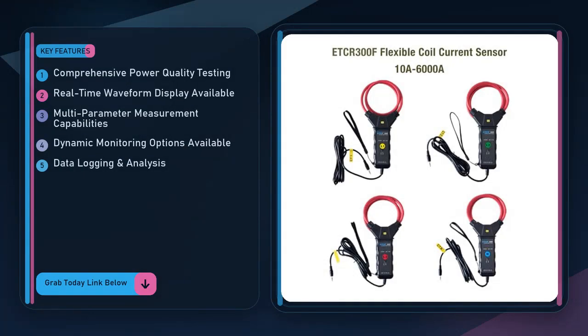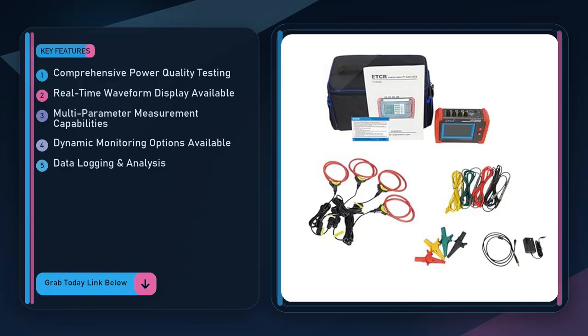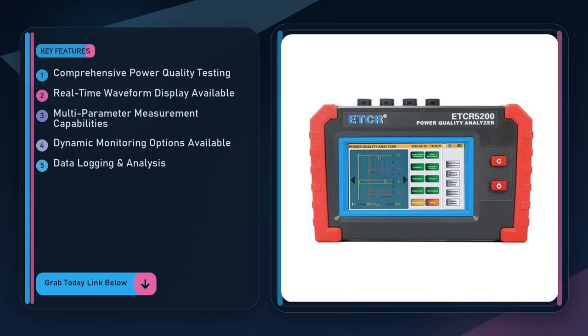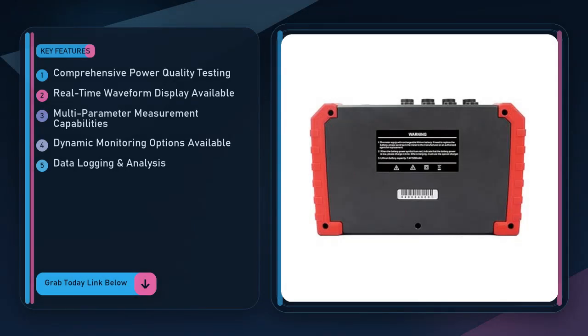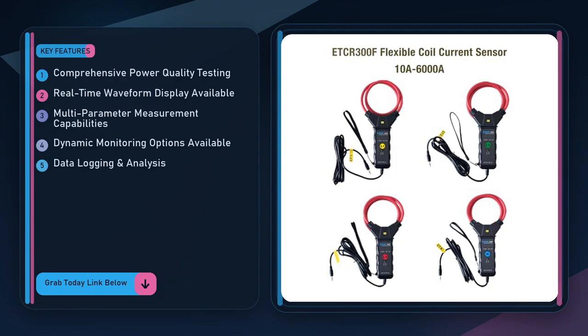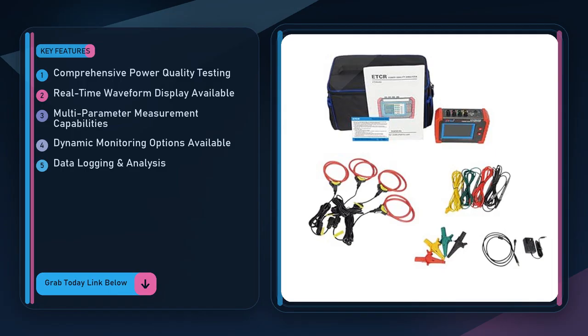Let's get into a couple of concrete scenarios to illustrate the value. A plant manager I spoke with was dealing with frequent tripping of a 400A breaker feeding a set of conveyor belts. By installing the ETCR5200 on one of the phases and leaving it to log for a week, he discovered a pattern. Every time a large air compressor kicked in, the voltage dip on that phase exceeded the breaker's trip curve by just enough to cause a nuisance trip.